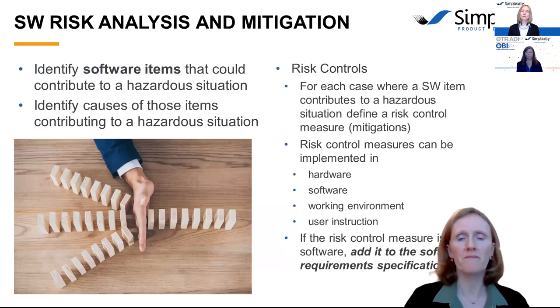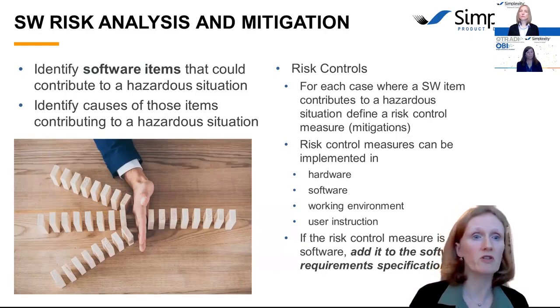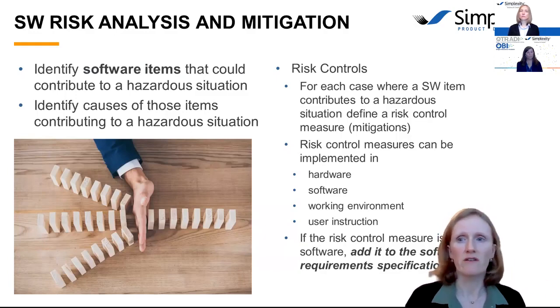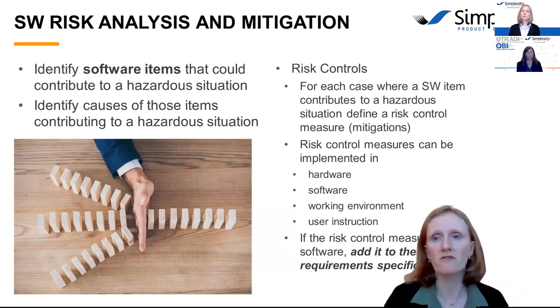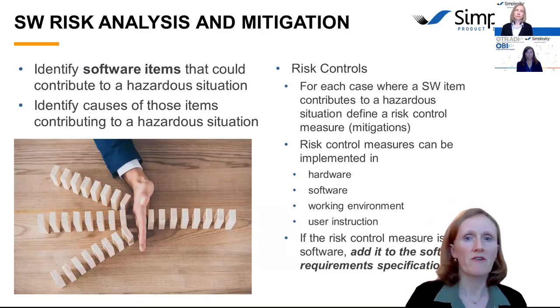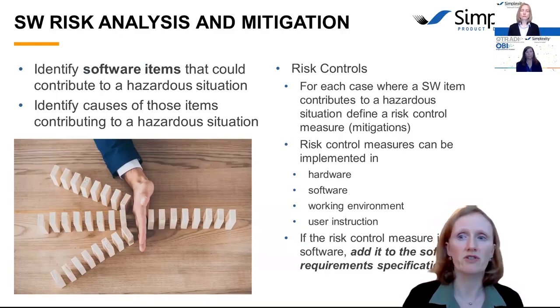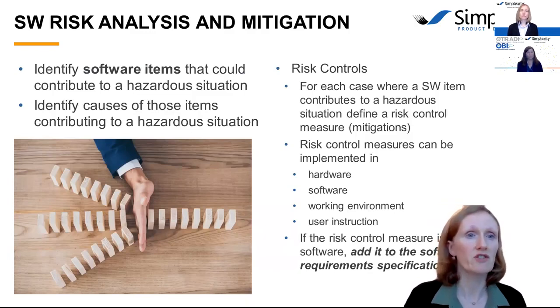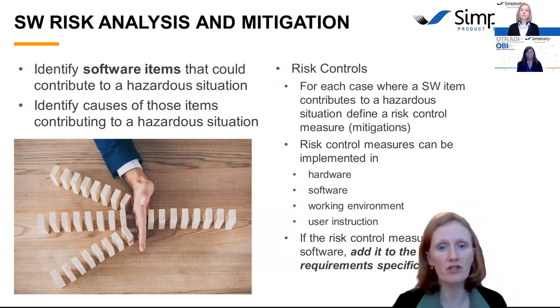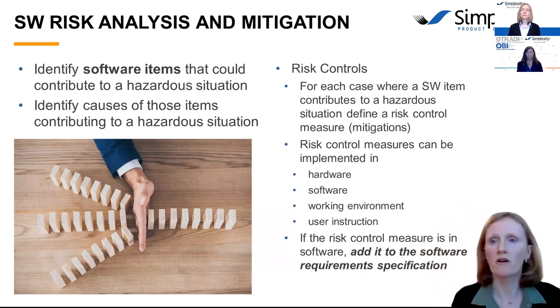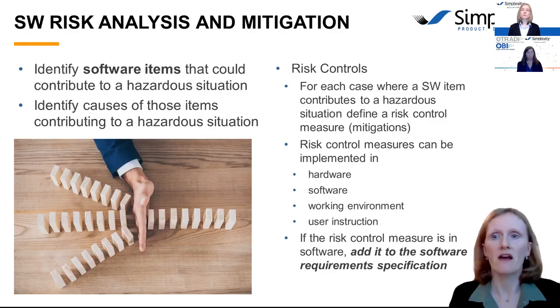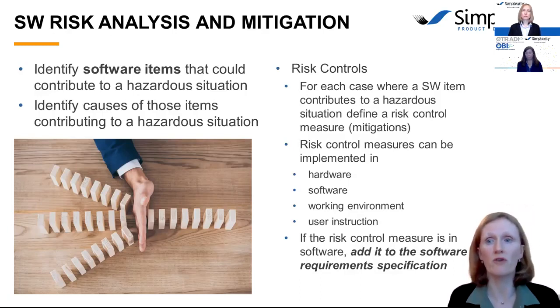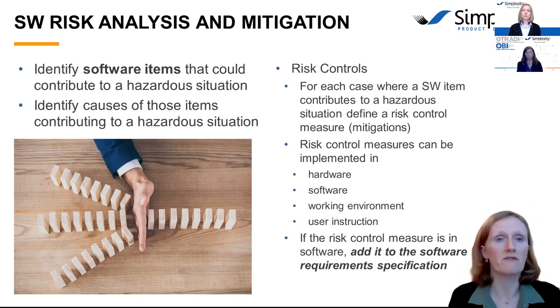So specifically for software, recall that in the architecture, we defined software items. During the software risk analysis, we would identify and list any of those items that could contribute to a hazardous situation. This usually involves a giant spreadsheet, either as part of the system hazard analysis or a separate spreadsheet. And then you would identify the causes of those items contributing to a hazardous situation. This could be a software bug that fails to sound an alarm, or a missing specification where no alarm was required. It could be how the software reacts to a hardware failure. If you lost connection to a sensor, for example, does the software crash, or does it put itself in a safe state? And what does a safe state even mean for your system?